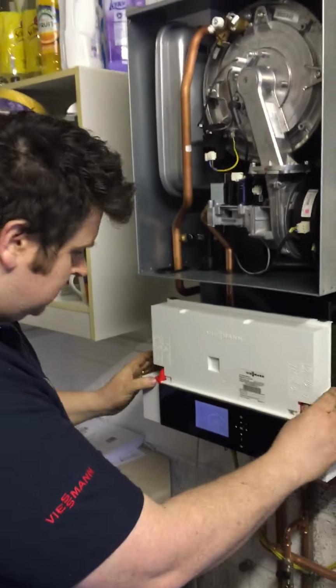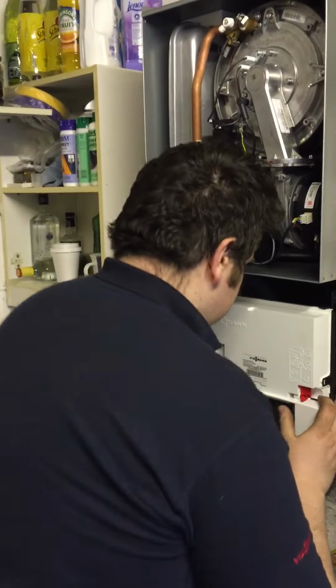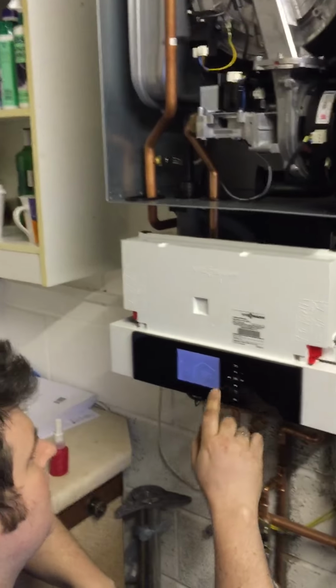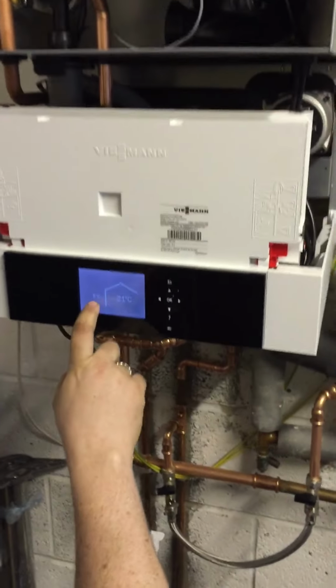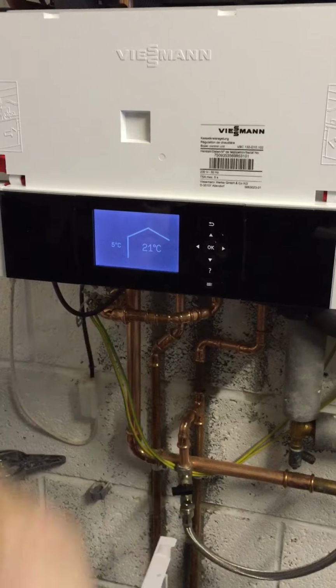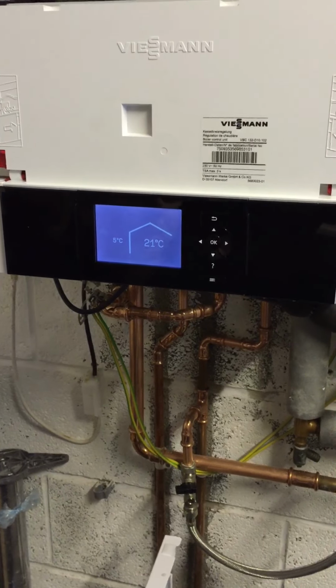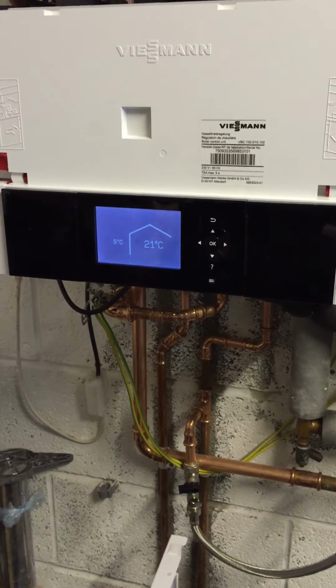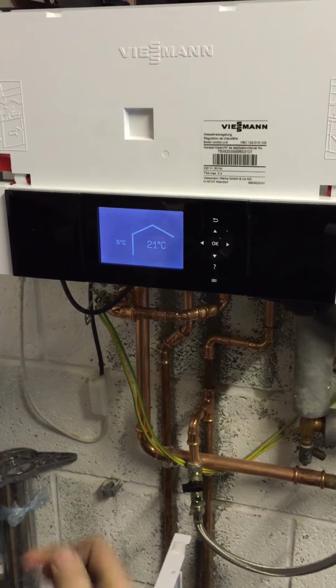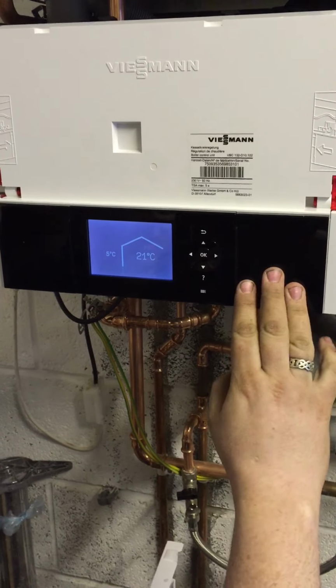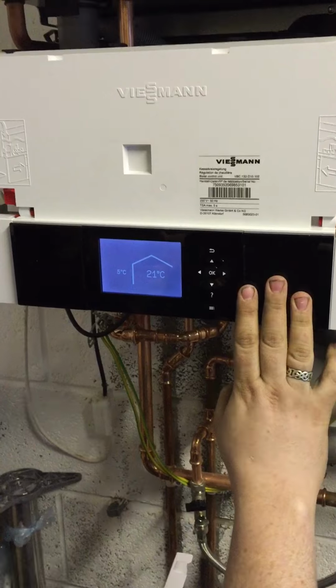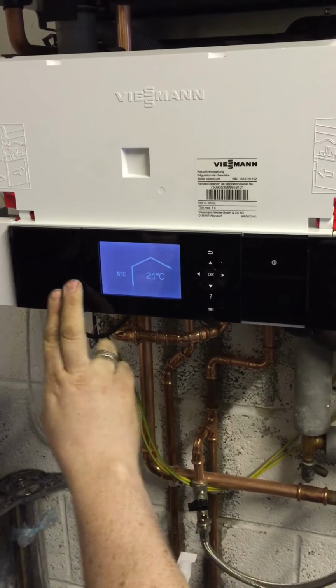We'll have a look at the controls. Talk you into the controls. So as you can see on the front of the controls here, we've got the outdoor sensor. Today it's 5 degrees outside. We're looking to maintain 21 degrees at the moment. We're still in commissioning mode, or certainly I'm still commissioning the boiler, so I've set the curve to maximum just to get some heat into the building, because the heating's been off for a fair few hours now. So the flap's open like that.